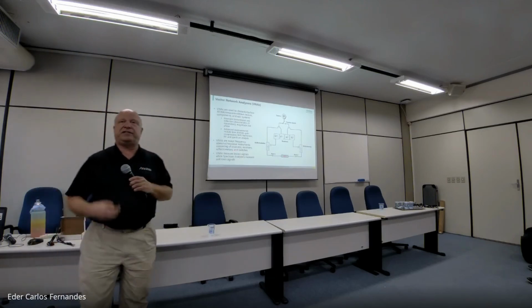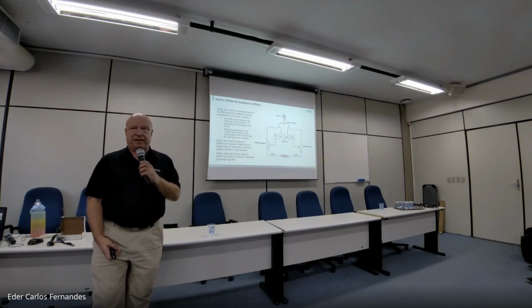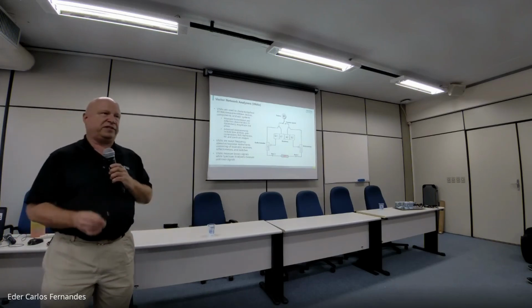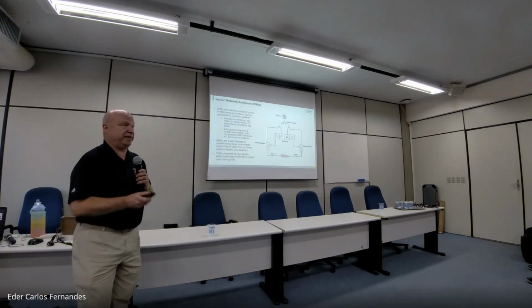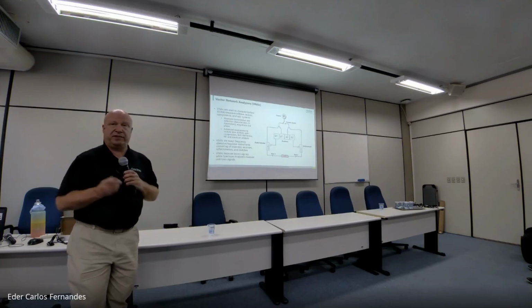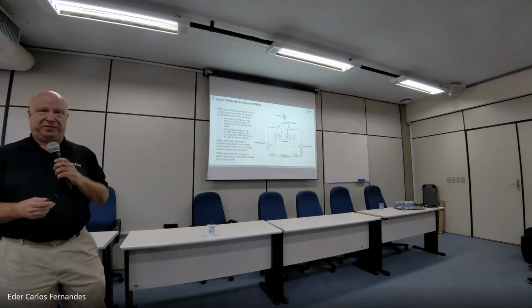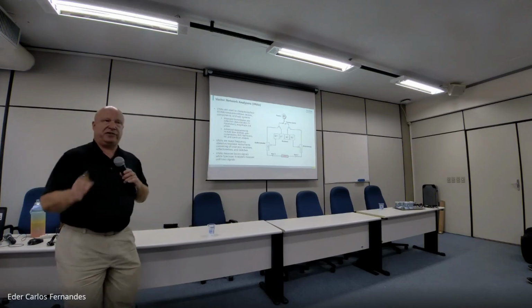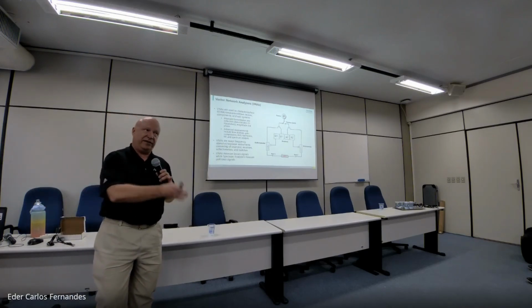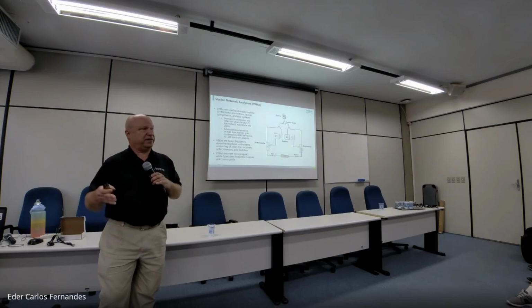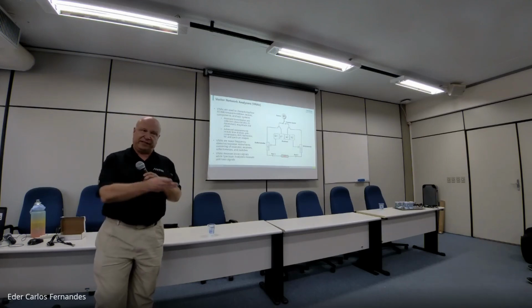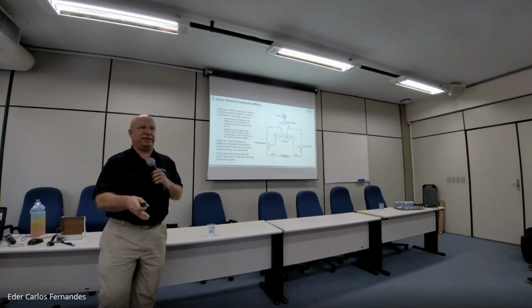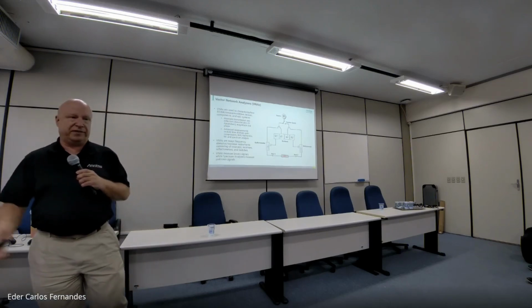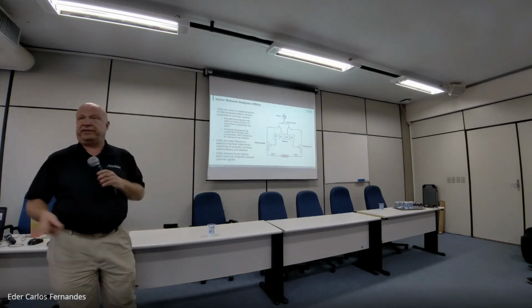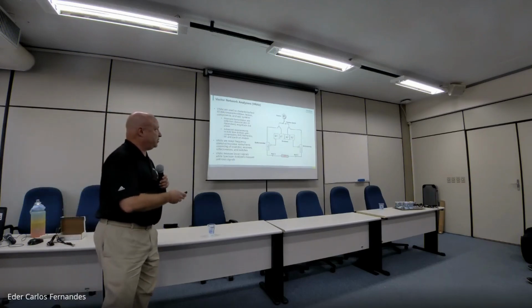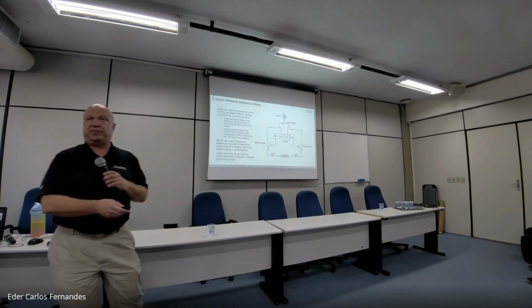So this is one of my favorite things. If I was to describe the difference between a VNA and a spectrum analyzer: a VNA measures known signals because we're generating them in the box and sending them out to the device. So we know what we're generating, and we know, therefore, what we're going to measure. But in the case of spectrum analyzers, you could get a little of both. You might have signals that you know are there and you'll find them, but you're also going to find signals that are unknown that you didn't know were there. A VNA is not designed to do that. A VNA is designed to measure known signals, whereas a spectrum analyzer or a power meter would be doing both known and unknown. So that's an important distinction between VNAs and spectrum analyzers.